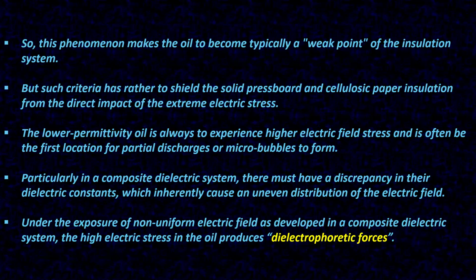So, this phenomenon makes the oil typically a weak point of the insulation system. But such criteria also shield the solid pressboard and cellulosic paper insulation from the direct impact of the extreme electric stress. The lower permittivity oil always experiences higher electric field stress and is often the first location for partial discharges or microbubbles to form.